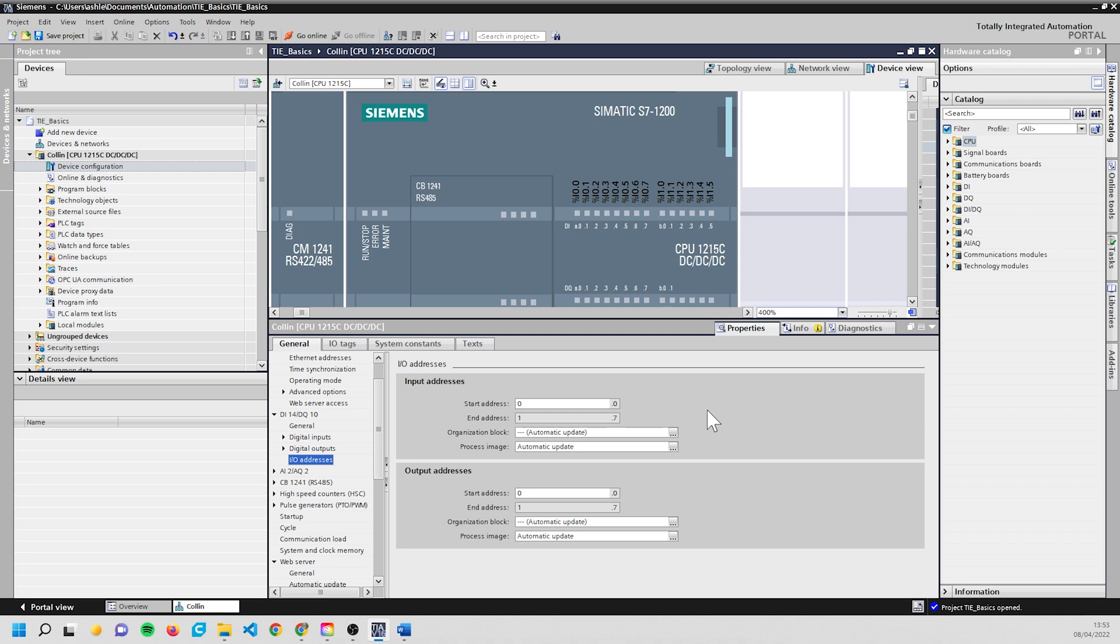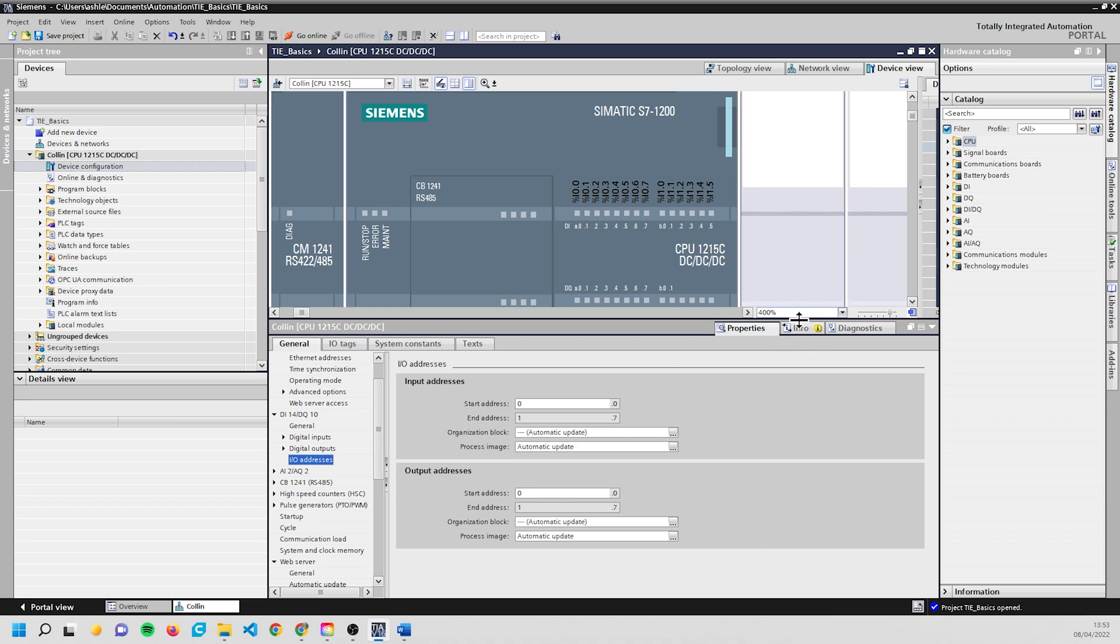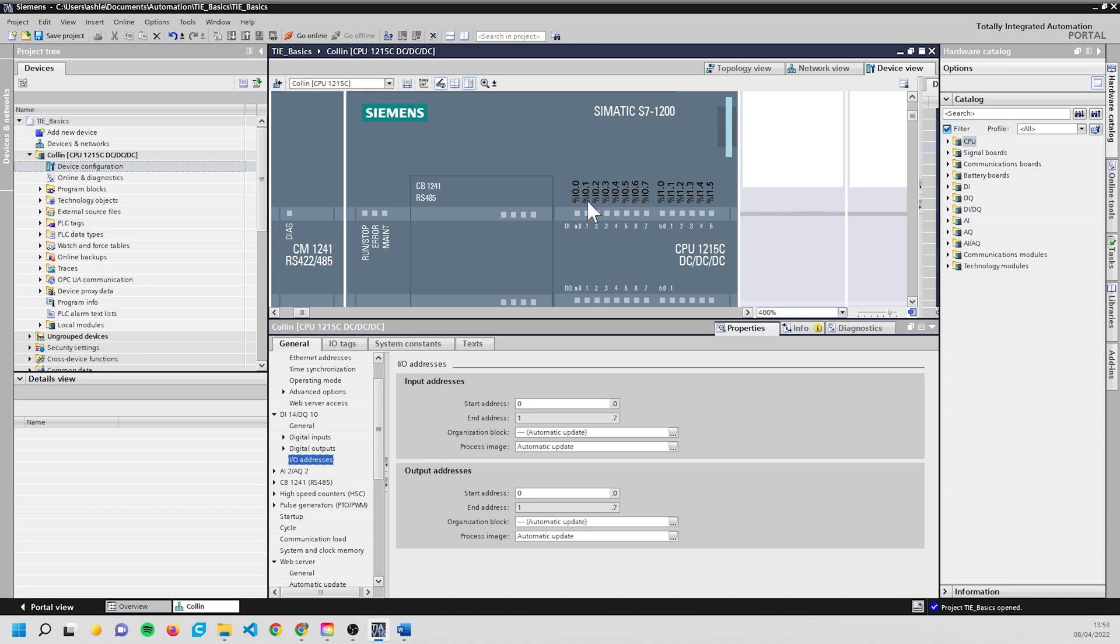Okay, so this is how I usually have it set up, especially on the actual CPU. I wanted to have a chat about this because when you add modules to the side - say you buy another input module or output module - those numbers don't always add up. If you're jumping through memory, you might just want to index through incrementally and if these all go from 0.1 and then suddenly jump to 7.1, it kind of throws you off a little.